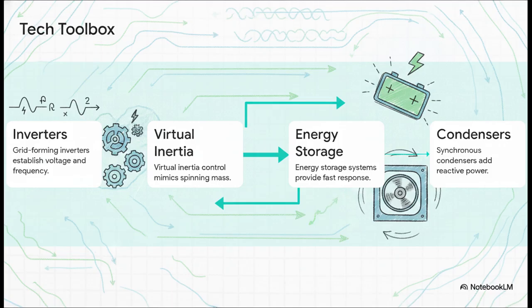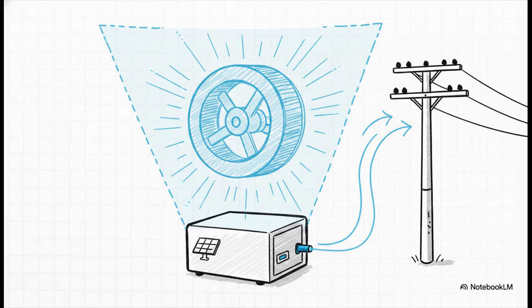But what's really mind-blowing here is that concept of virtual inertia. We are literally programming advanced software control strategies to make a completely static, silent piece of electronics, like a solar inverter, adjust its power output instantly to mimic the exact physical behavior of a heavy spinning metal generator. We are basically tricking the grid into thinking the heavy metal is still there, artificially slowing down those dangerous frequency changes to keep the whole system stable.